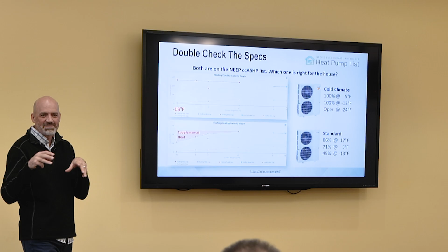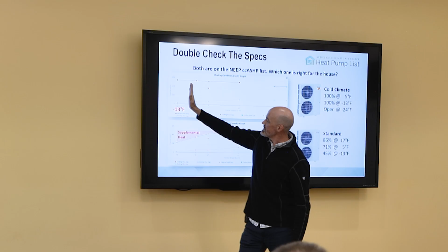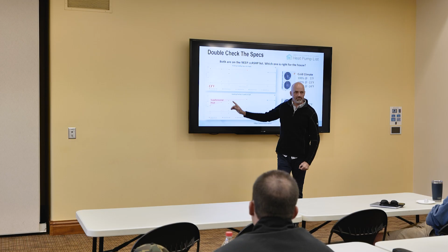But irrelevant, really. Because remember our demand, our load calc, our heating load slope looks like this. So we want to make sure that at our design condition, we're at or very near 100% covered, which is why having not only 100% at 5 is so important, but having this guy up here as well, right? And operation down to -20 whatever. This one will run down to -13, but you need a lot of extra supplemental heat to cover that. You're going to be paying a lot more, not only in the balance of system, the extra system to do it, but the additional less efficient cost. Does that make sense?